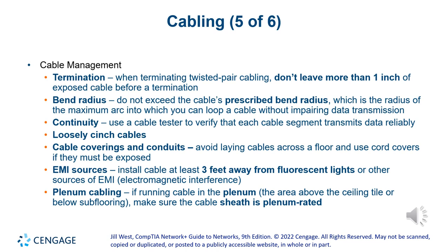I can't stress enough the EMI sources. 3 feet away is kind of the standard. Fluorescent lights, any motors, a microwave or anything like that. Even power lines, stay away from your power. Don't run your data next to your power.